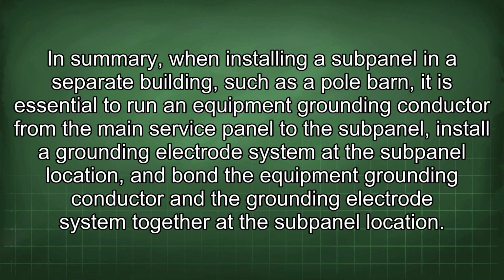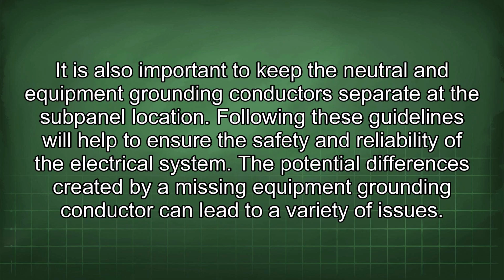In summary, when installing a subpanel in a separate building, such as a pole barn, it is essential to run an equipment grounding conductor from the main service panel to the subpanel, install a grounding electrode system at the subpanel location, and bond the equipment grounding conductor and the grounding electrode system together at the subpanel location. It is also important to keep the neutral and equipment grounding conductors separate at the subpanel location. Following these guidelines will help to ensure the safety and reliability of the electrical system.